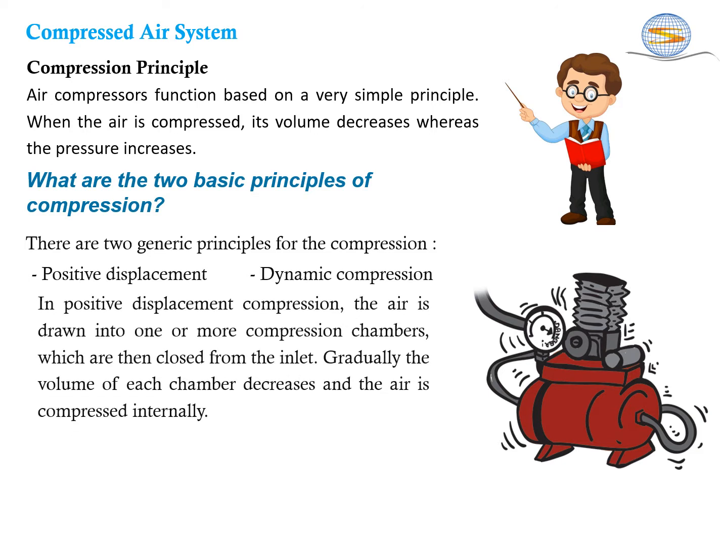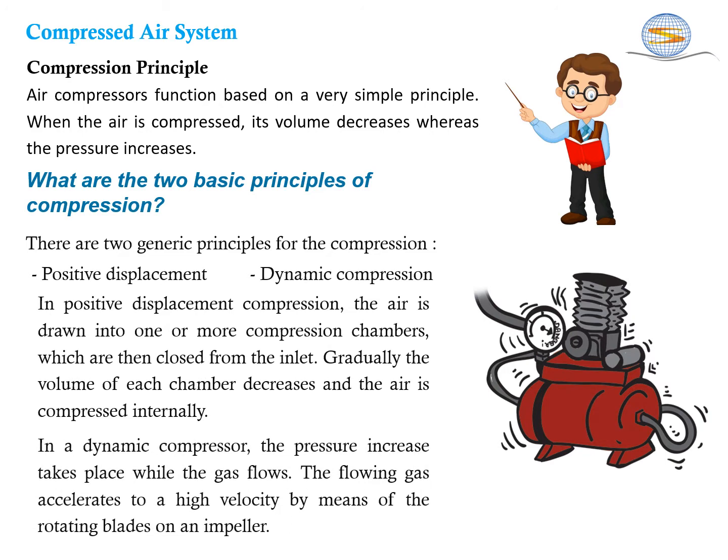In positive displacement compression, the air is drawn into one or more compression chambers which are then closed from the inlet. Gradually, the volume of each chamber decreases and the air is compressed internally. In dynamic compression, the pressure increase takes place while the gas flows. The flowing gas accelerates to a high velocity by means of the rotating blades on an impeller.